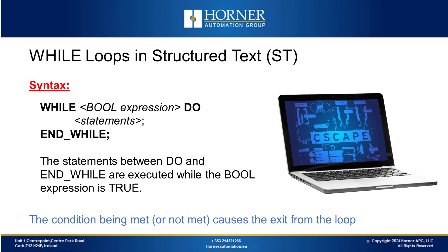Now we will look at the syntax for while loops, also using structured text. With while loops, the statements between the do and the end while statements are executed while the boolean expression is true. The condition of the loop being met or not met is what causes the exit from the loop. The potential for an infinite loop with a while loop is much higher than with a for loop, because it is easier to set up a while loop with a condition which will never change. So if the condition set for a while loop is never false, the loop will run an infinite number of times.